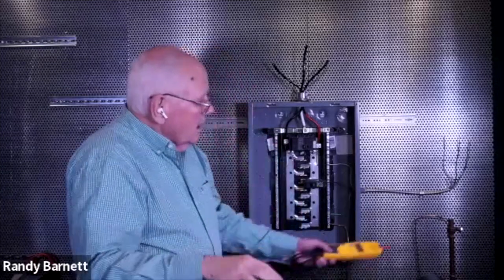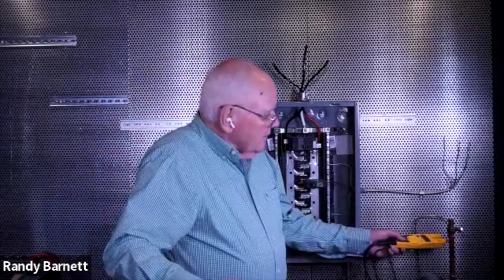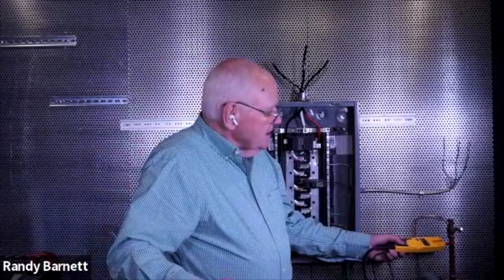Now, this is going to dissipate any voltage surges into the earth. My connections have to be made properly. 250.53 tells me that it has to be in contact with the earth for at least 8 feet. Also in 250.53, it'll tell me what happens if I'm driving this in and I hit rocks and I can't get it in. I can put it at a certain angle or dig a trench and bury it in. And all those specifics are covered in the NEC.